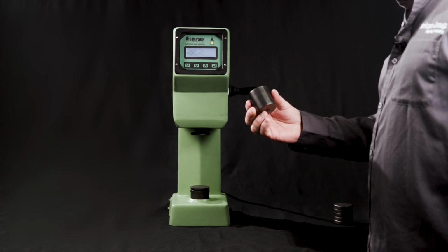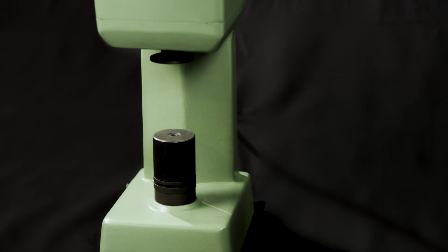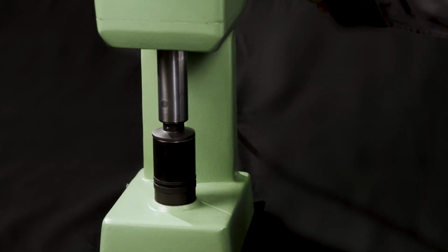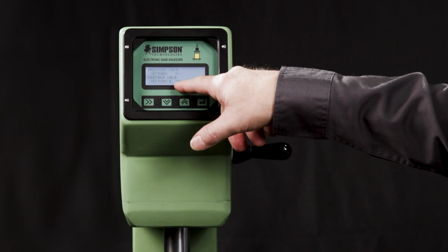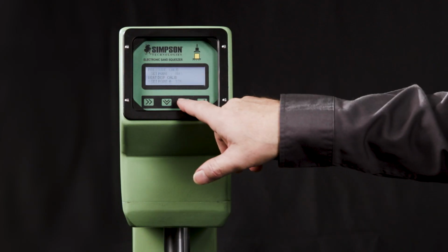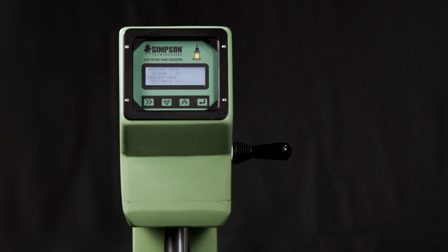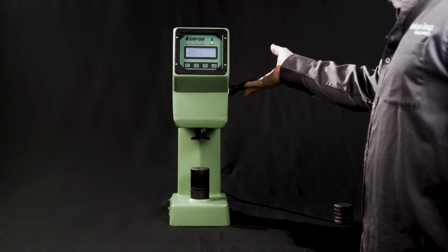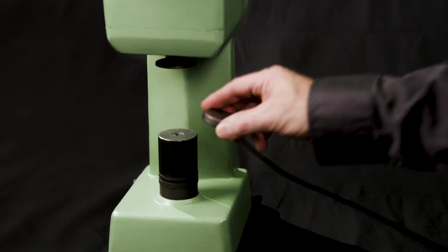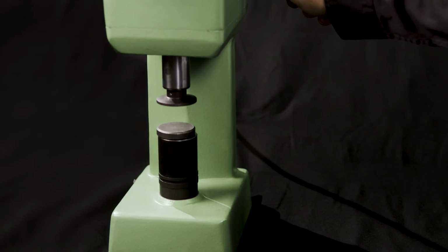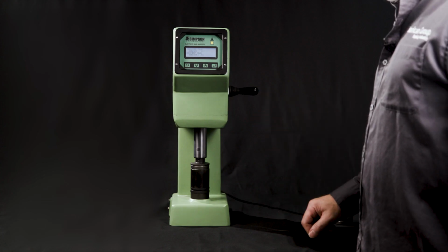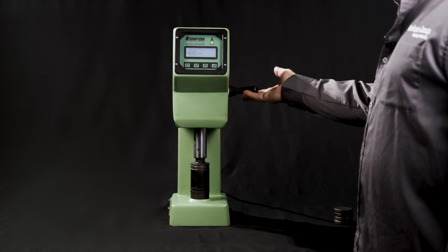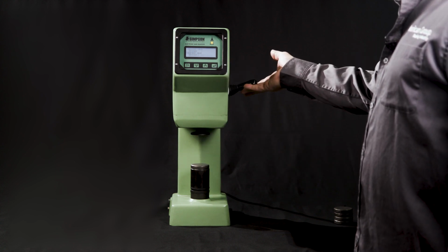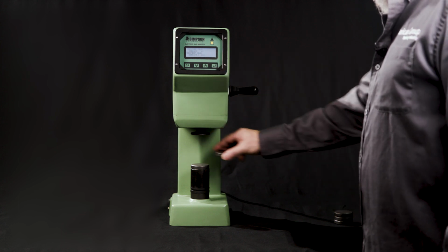We are going to put in our 50mm calibration plug onto the base. We're going to bring down our piston until this number down here stabilizes. Then we are going to press the up arrow. It's going to blink on and off, and you will see that the set point for that is going to change from 0 to 1. Bring the piston back up. Then we are going to be putting in our 10mm plugs and doing the same thing. Bring the piston down, let it stabilize, press the up arrow, then bring the piston back up. It went to set point 2.